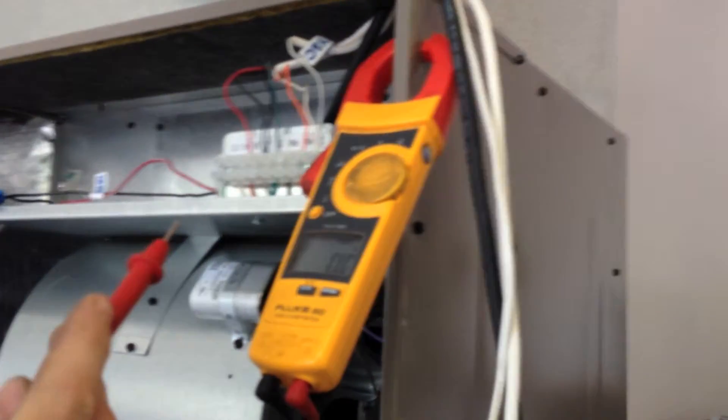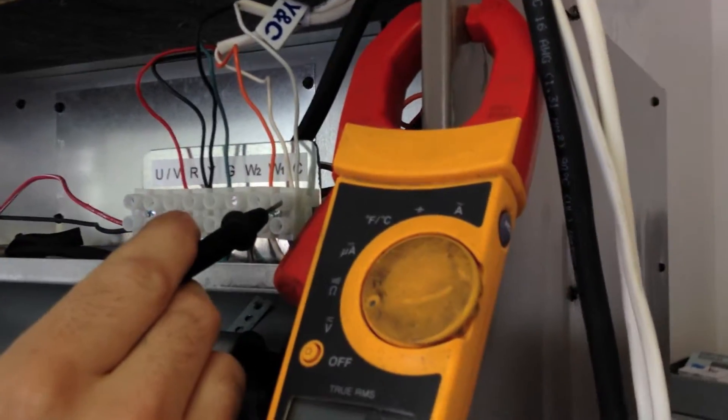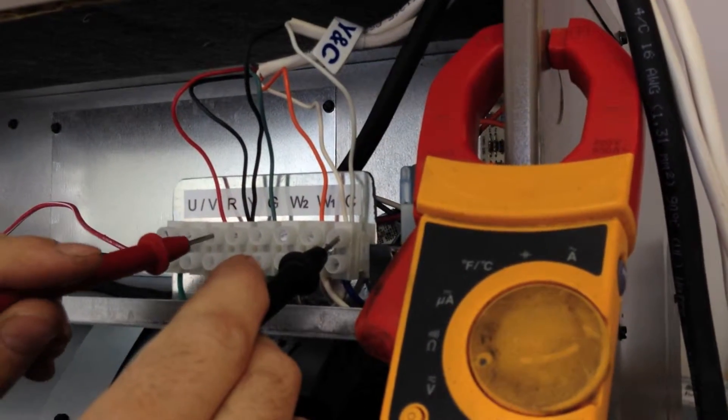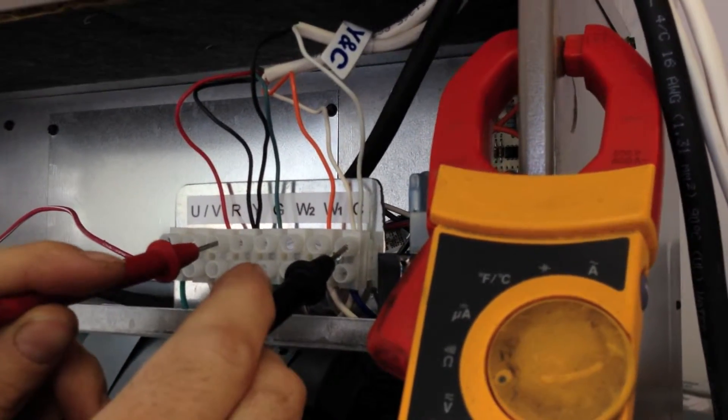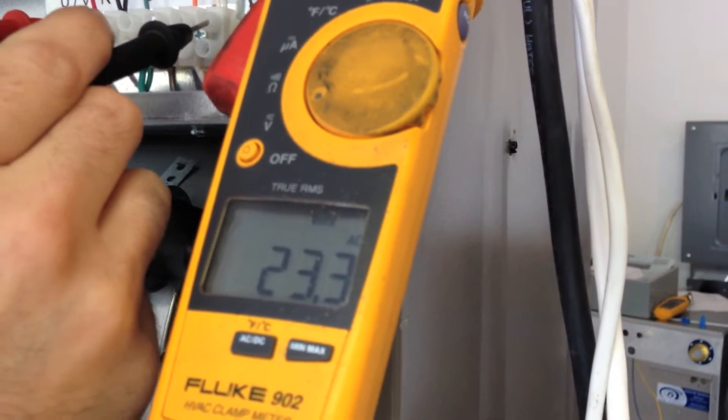Next, we're going to take our probes and we're going to put our black onto our C terminal and our red onto our R terminal. And if you look at our voltage screen, we have 23.3 volts, so we have voltage.